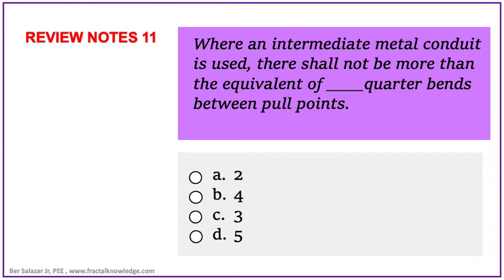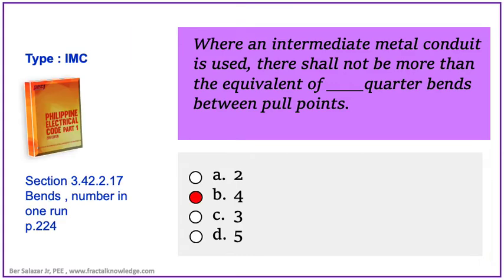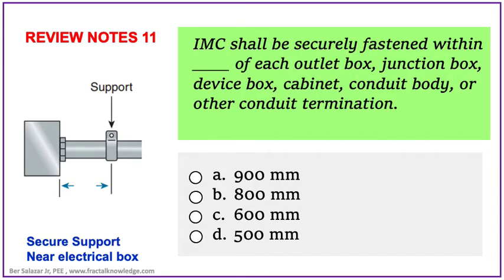Another problem regarding IMC asks: if an IMC is used, there shall not be more than the equivalent of blank quarter bends between pull points. How many maximum quarter bends between pull points is allowed — two, four, three, or five bends? The answer is letter B: four quarter bends between pull points. You can check it in section 3.42.2.17, page 224, for IMC bends number in one run.